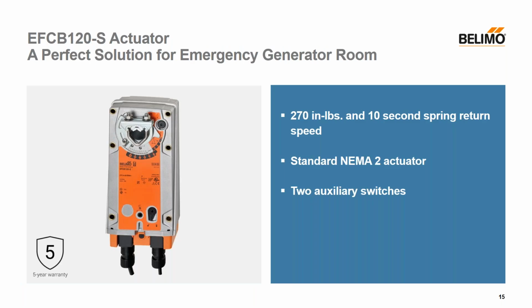Next, we have the EFCB 120-S actuator. The torque offering is 270 inch-pounds and a 10-second spring return speed. You may know that we offer a NEMA 4 version of this, but our customers have been asking for a NEMA 2 version, so now it is our standard offering in our PGPL. And this can operate damper sizes up to 90 square feet.